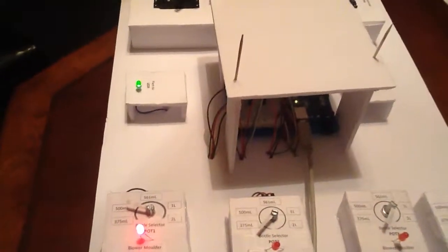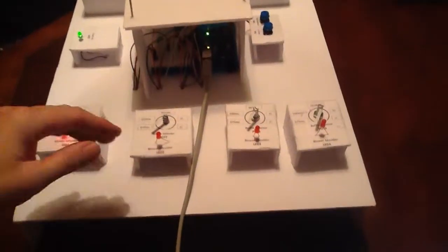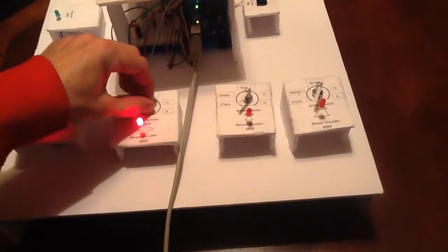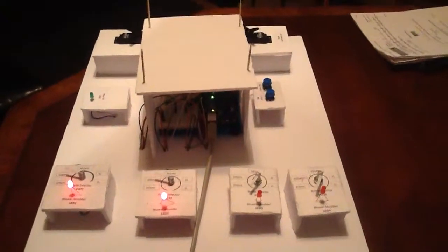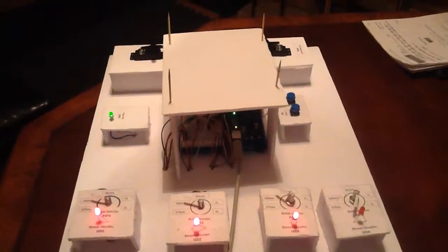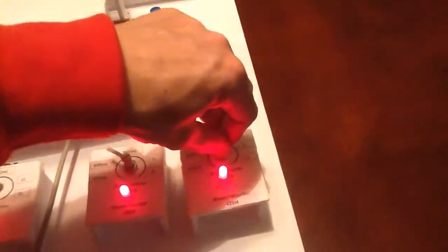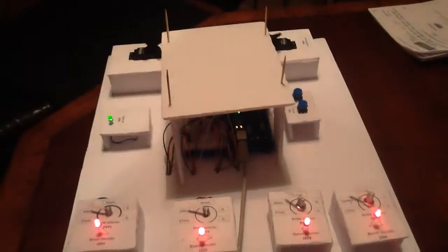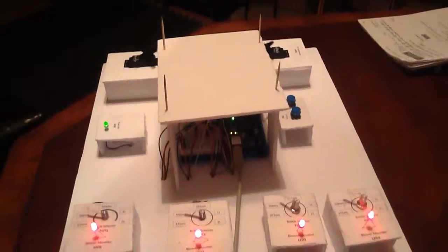You can see from the light of the plant air that we are creating excessive air, and we have air being produced at the air compressor. Now if we switch number 2 on, so now number 2 is on, we still are within the 70% of air compressor number 1. If we turn on number 3, now all of a sudden we're requiring that extra blower motor. And then if we turn on the last one, did you hear that? That was all of a sudden the second blower motor changing direction because we now require that 100%.